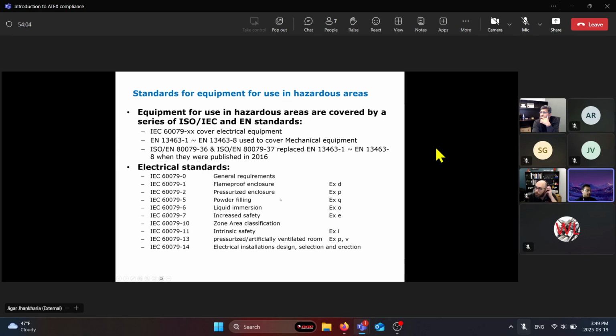So moving back to the different standards, -1 is for a flame-proof enclosure. In other words, an explosion-proof enclosure which contains any explosions. They would be contained inside the explosion-proof enclosure itself. Pressurized enclosure. There's different types of pressurization, type Z, type X, and type Y.